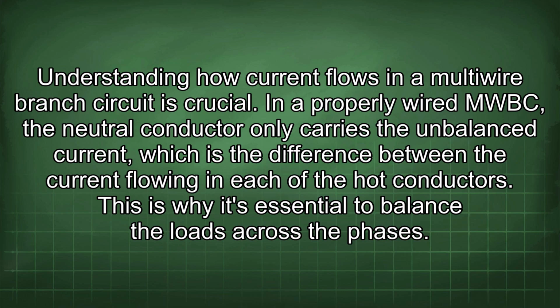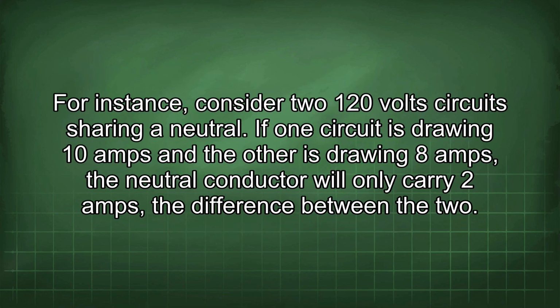In a properly wired MWBC, the neutral conductor only carries the unbalanced current, which is the difference between the current flowing in each of the hot conductors. This is why it's essential to balance the loads across the phases. For instance, consider 2 120-volt circuits sharing a neutral. If one circuit is drawing 10 amps and the other is drawing 8 amps, the neutral conductor will only carry 2 amps, the difference between the two.